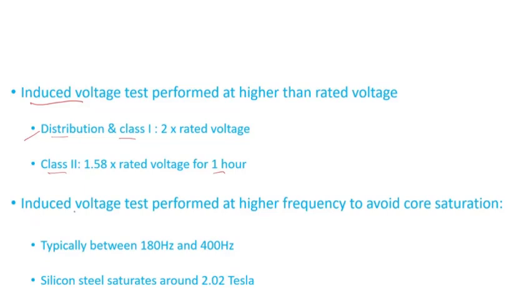The induced voltage test is also performed at higher frequency, and the reason is to avoid core saturation. We'll see an example of why we increase the frequency. Typically the frequency is between 180 Hertz and 400 Hertz, and one thing to keep in mind: silicon steel material saturates around 2.02 Tesla. That's really the limitation for the core steel.